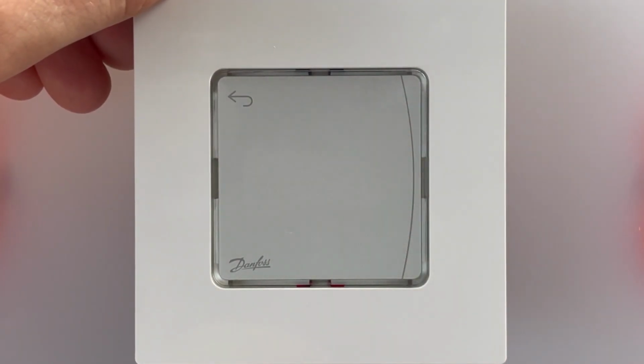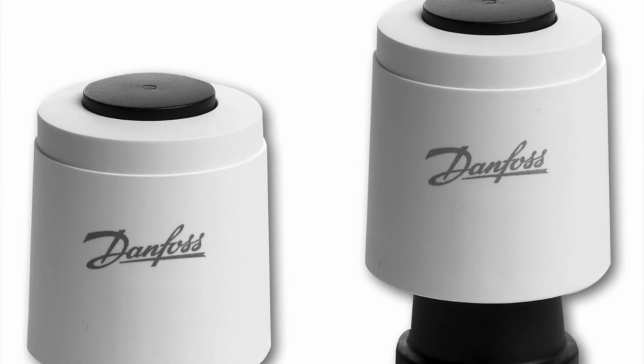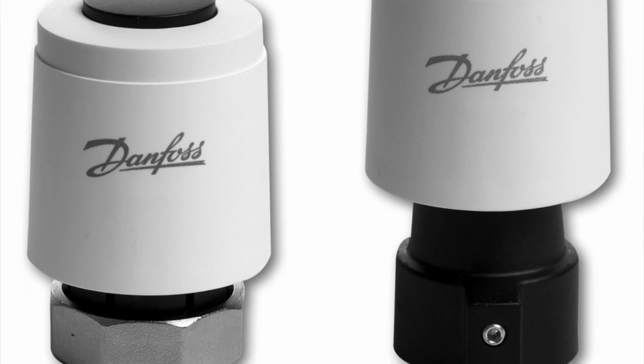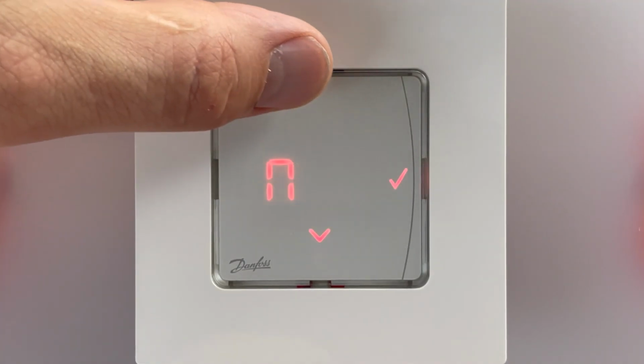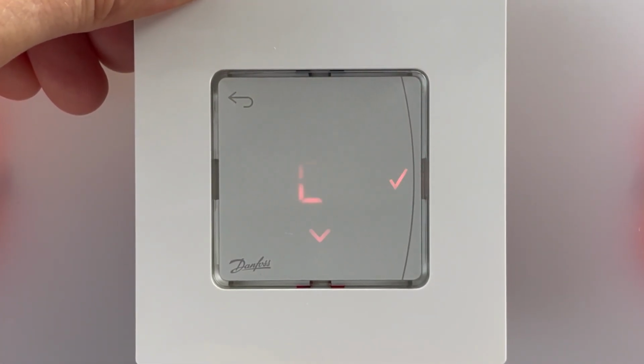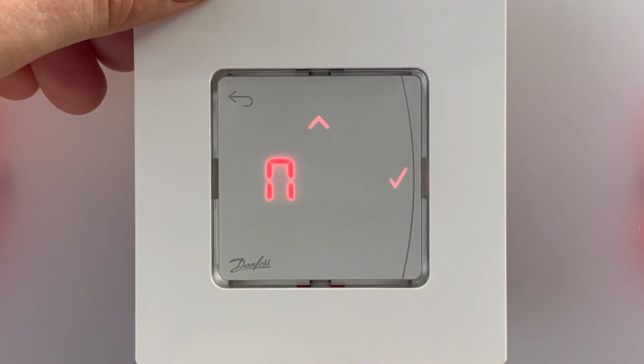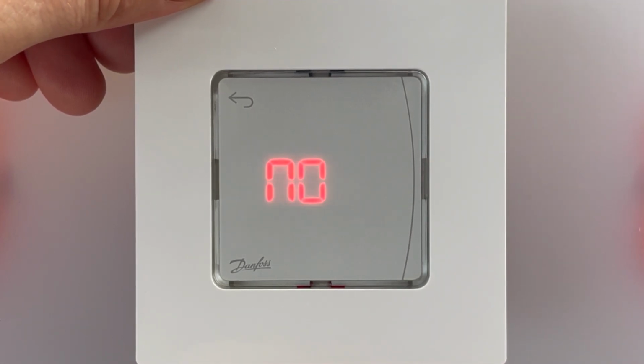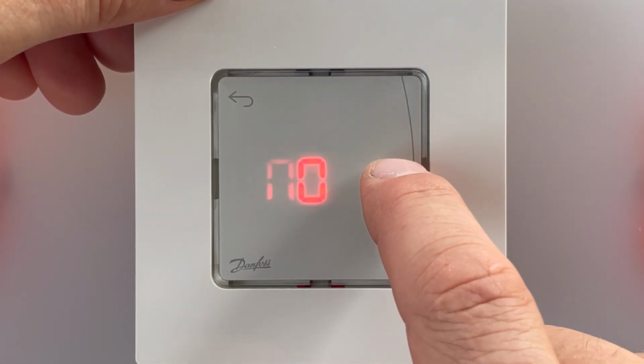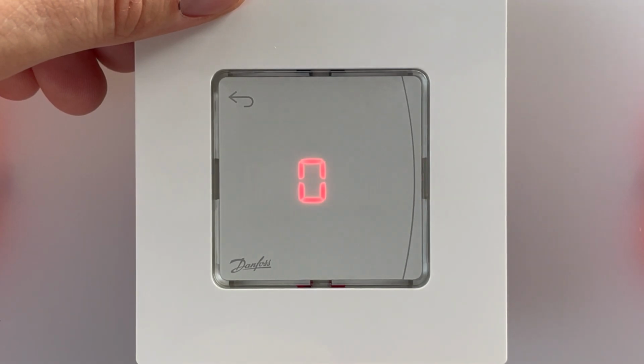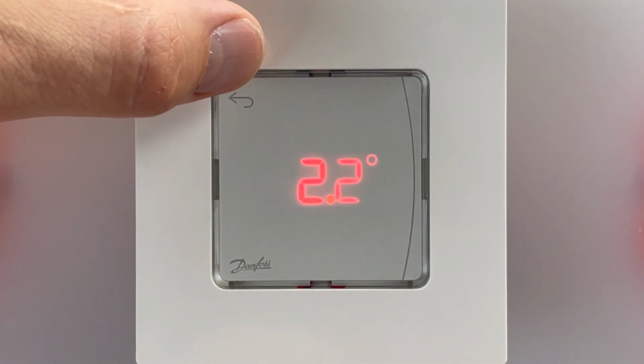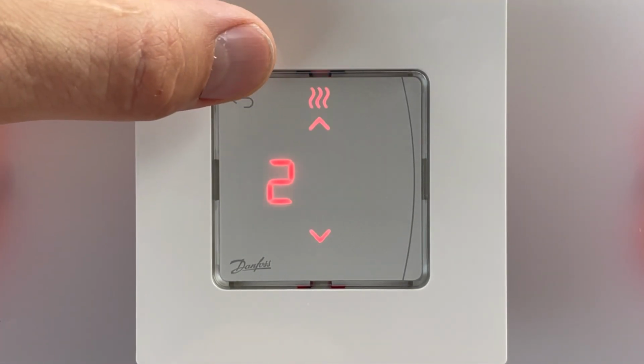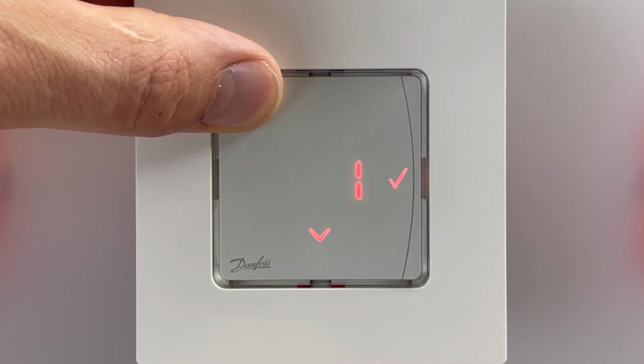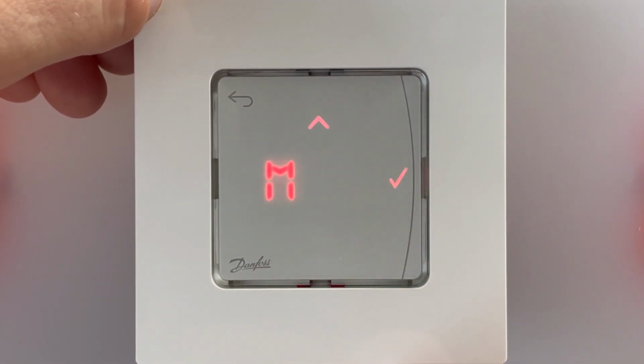Menu 3 is the type of actuator. It can be NC type or NO type. It depends what kind of actuator we have connected. Normally closed means without electricity it is closed, and a normally open actuator is without electricity open. Confirm, let's say we have NO, normally open actuator, and we enter menu 4.